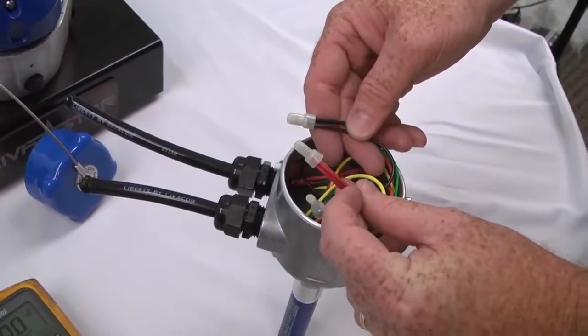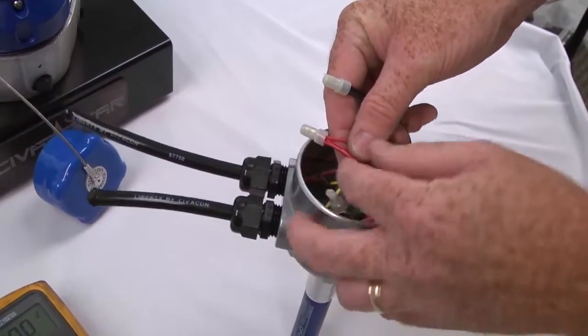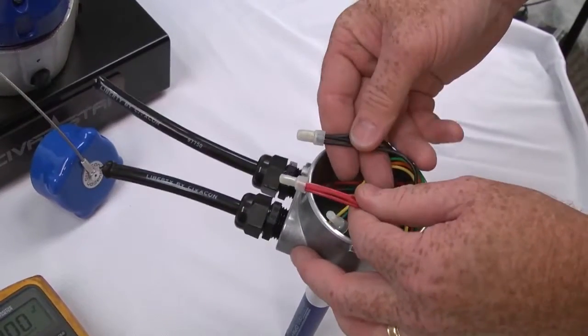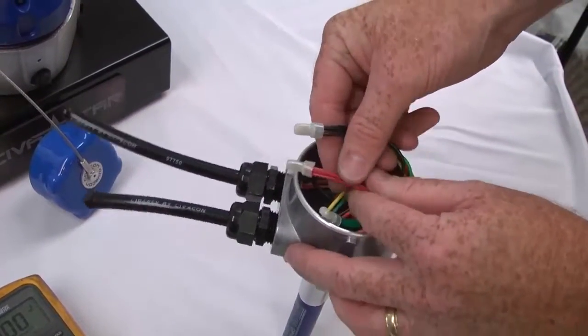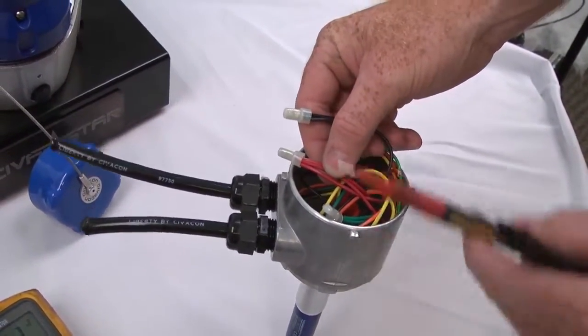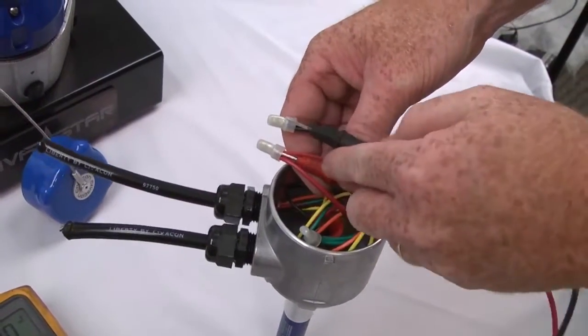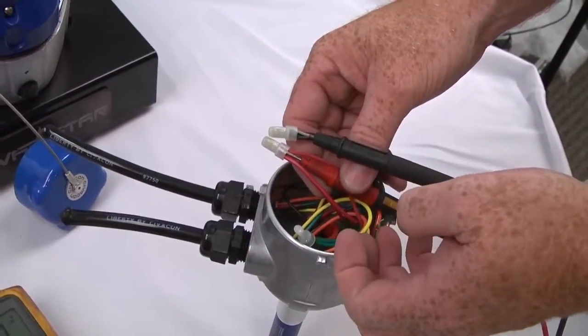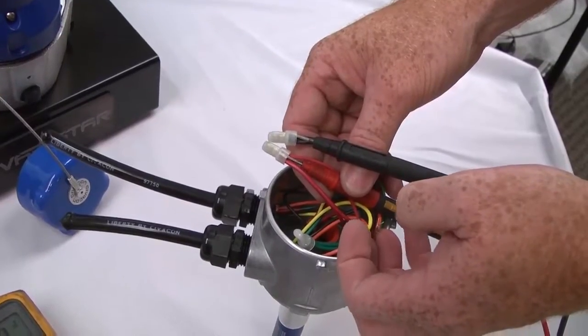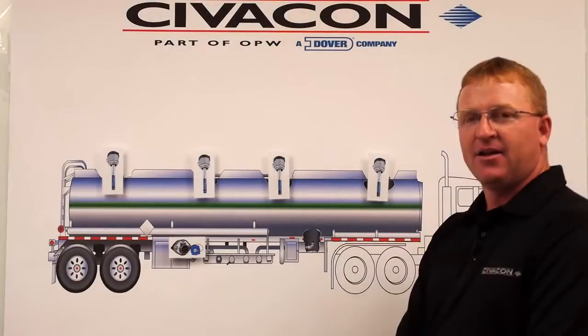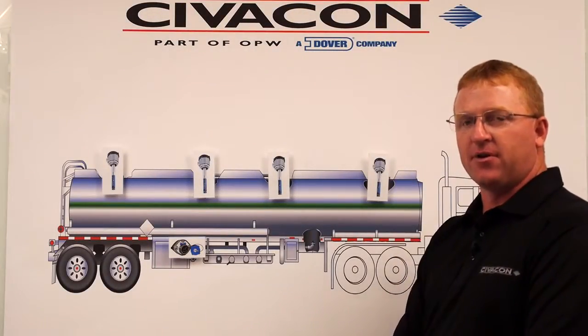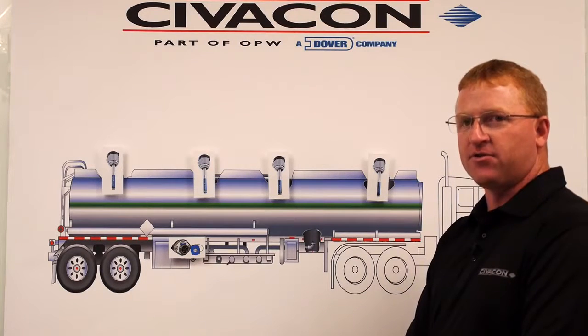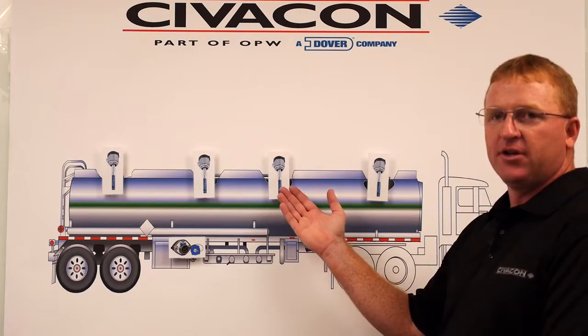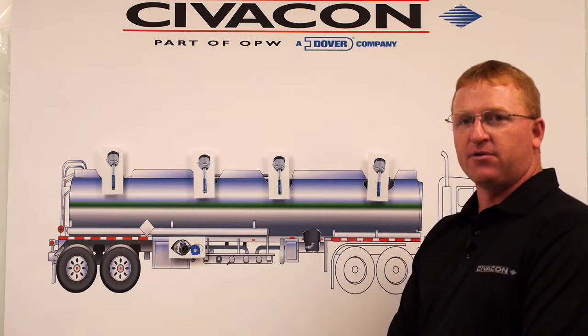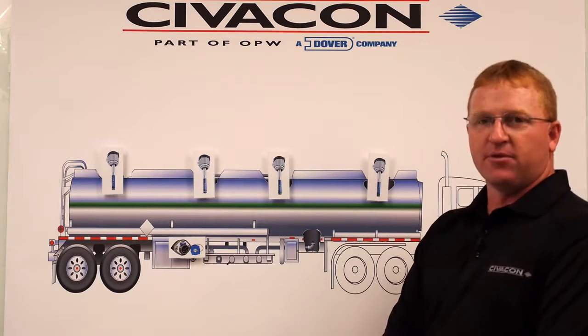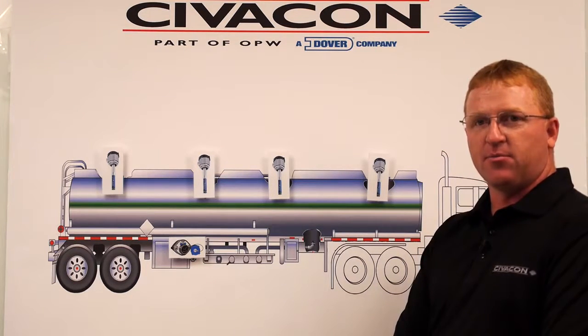If you've verified that all connections are free of corrosion and that the crimps are properly secured, you can check the voltage at the probe that is showing the fault. Simply connect your voltmeter to the red and black wire. The reading should be anywhere between 8 and 24 volts. At this point, if you verify that all the crimp connections are secure and free of corrosion, and they have the proper voltage at the probe that is showing the fault, now you would replace it with a new probe to see if that cures the problem.